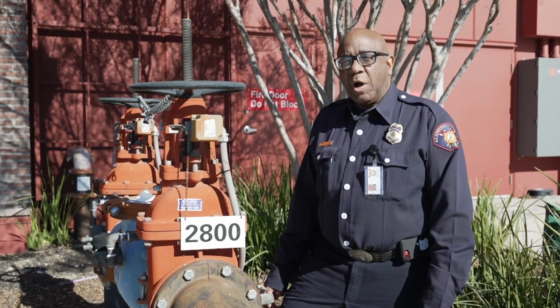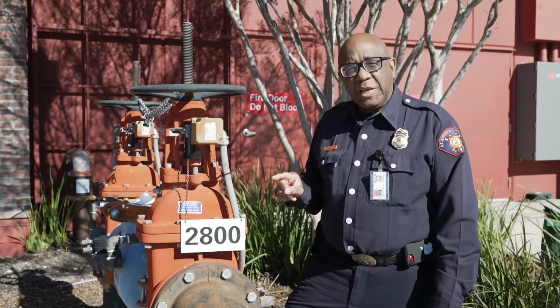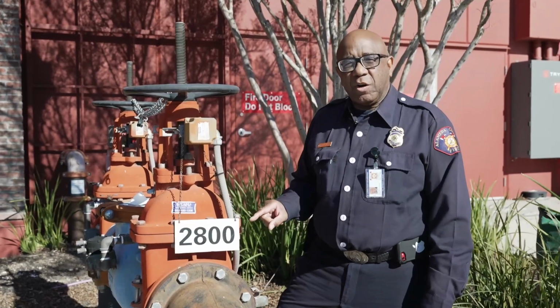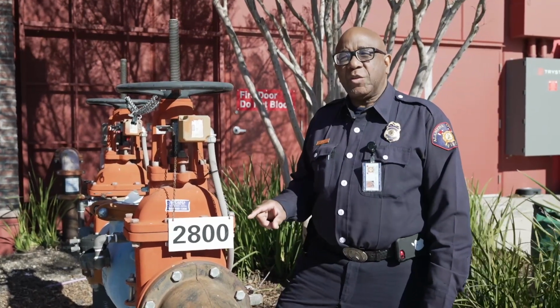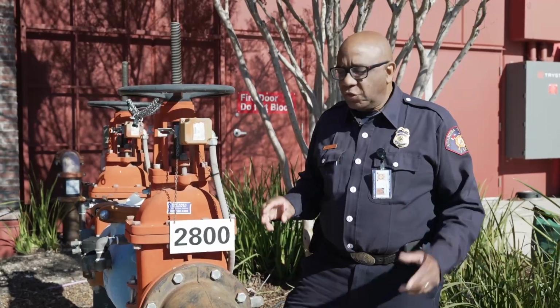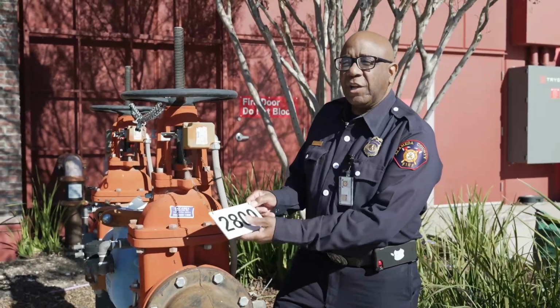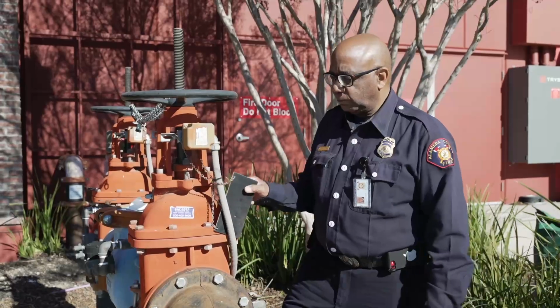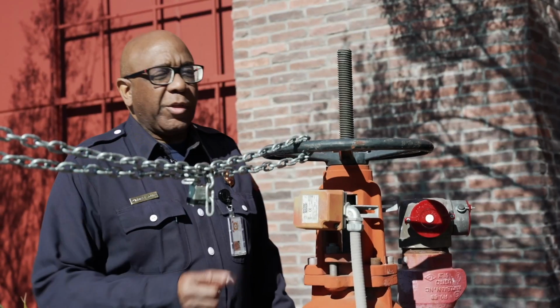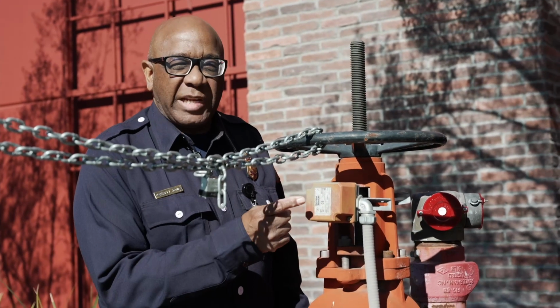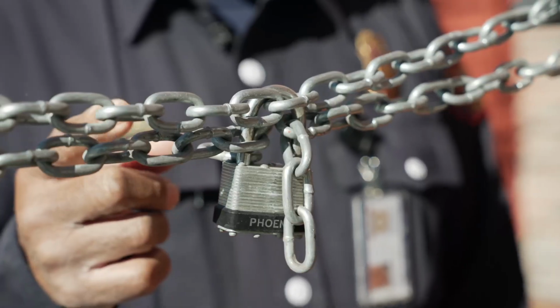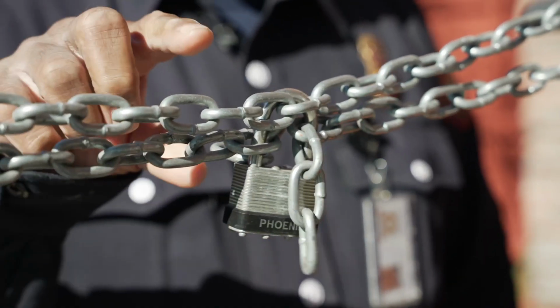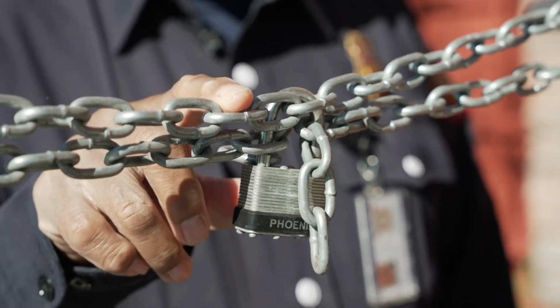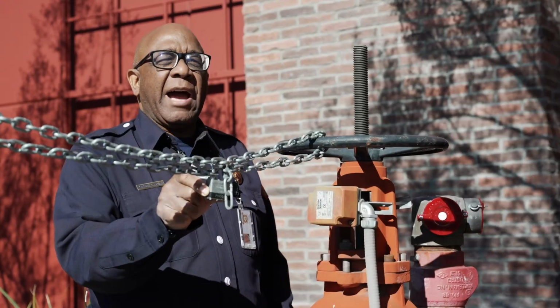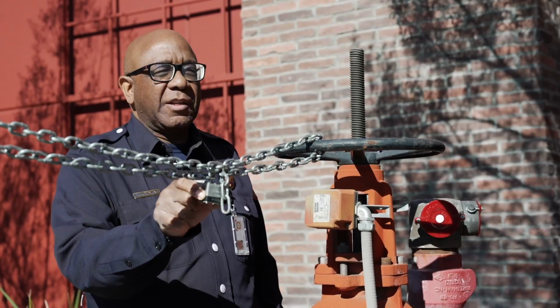On our OS&Y valves, they each need to be identified as to the area they serve. It's important that those signs are there. After your inspection is over, you might want to turn it over so it doesn't get weathered. Although the OS&Y has tamper protection, we generally require a chain and lock, breakaway lock on there. If that's damaged or broken, you can have that as a violation to have them replaced.